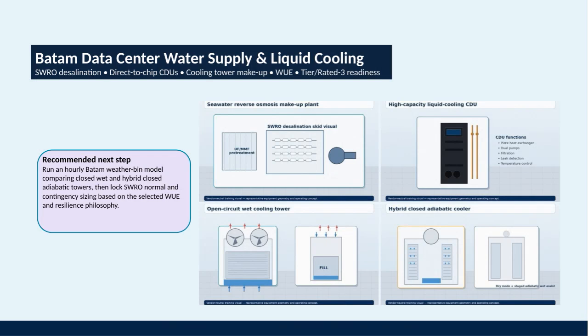Here we focus on the Batam Data Center's water supply and liquid cooling strategy. Key components include SWRO desalination, which provides a reliable source of fresh water, direct-to-chip cooling distribution units that enhance cooling efficiency, and using cooling tower makeup water effectively. Water usage efficiency, or WUE, is a critical metric here, along with ensuring the data center meets Tier 3 readiness standards for reliability and redundancy.